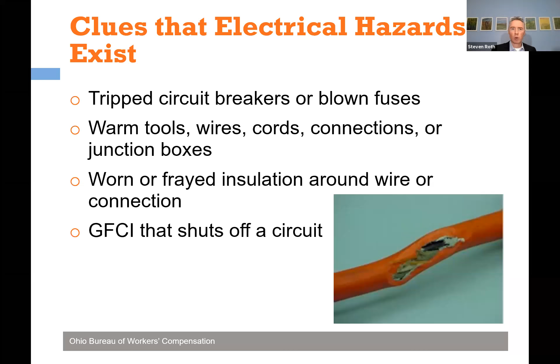Clues that you've got problems: breakers that keep tripping, tools or cords that are warm - you drew too much current - or a GFCI that keeps tripping. Those are signs we've got an electrical problem. It could be the GFCI itself, but oftentimes it's really the piece of equipment.